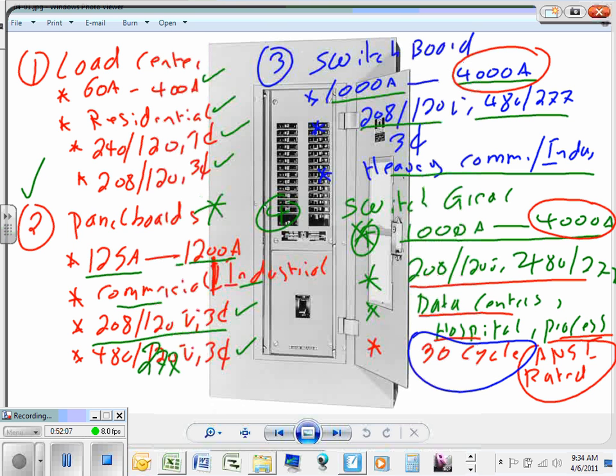This circuit breaker, guys, if you have a short circuit right in any of these branches right now, it's rated for 3 cycles. What's a cycle? 3 cycles, 3/60 of a second, so 1/20th of a second. So this circuit breaker is rated to trip at 1/20th of a second. See how fast that is?